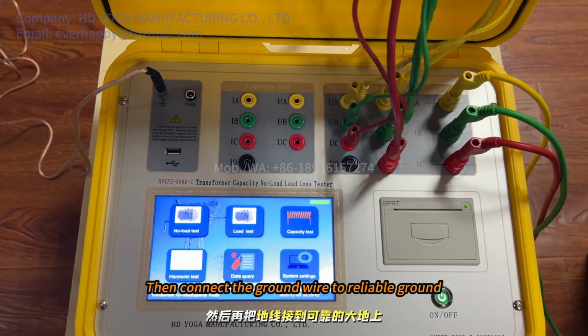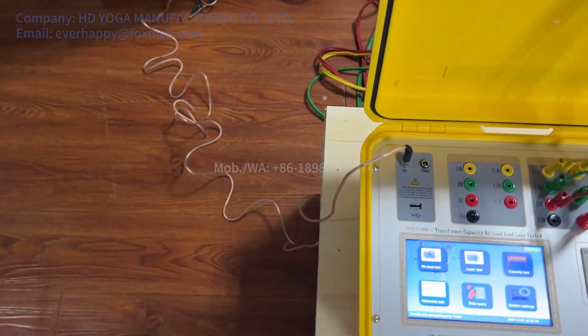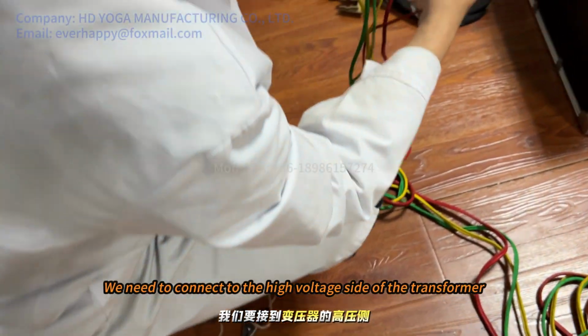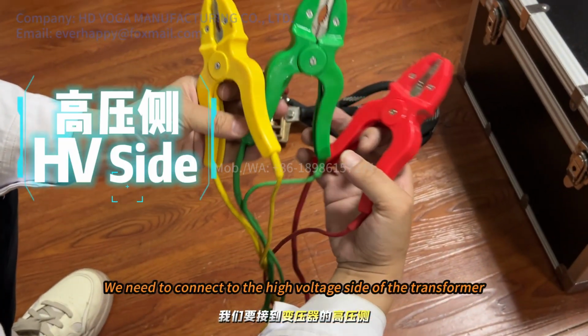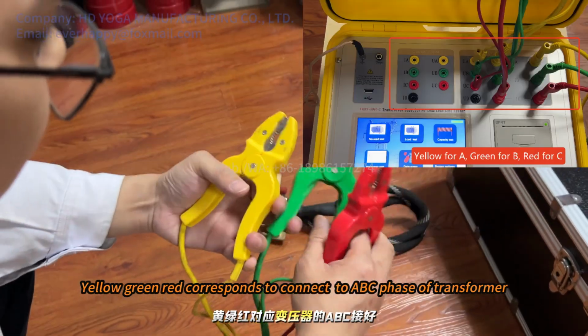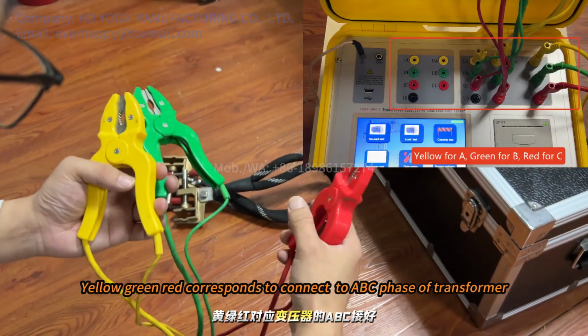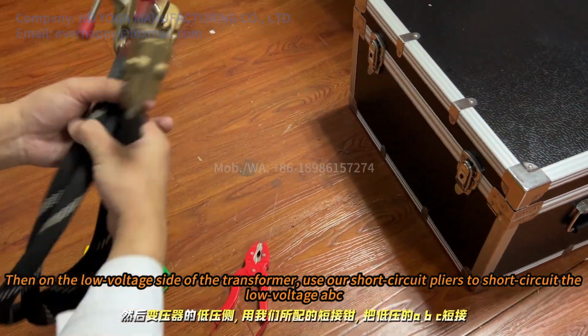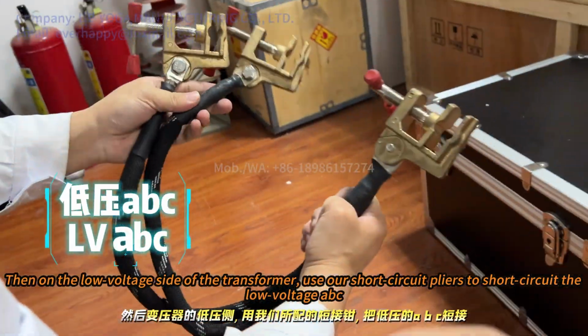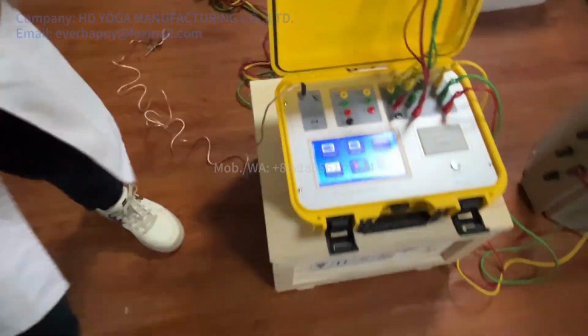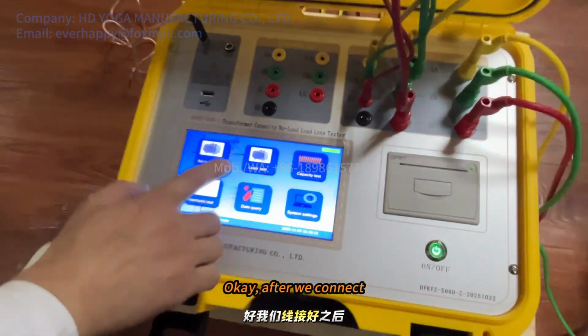Then connect the ground wire to a reliable ground. Then the 3 yellow, green and red clips we need to connect to the high voltage side of the transformer. Yellow, green, red correspond to the ABC phases of the transformer. Then on the low voltage side of the transformer, use our short circuit pliers to short circuit the low voltage ABC. Okay, after we connect.